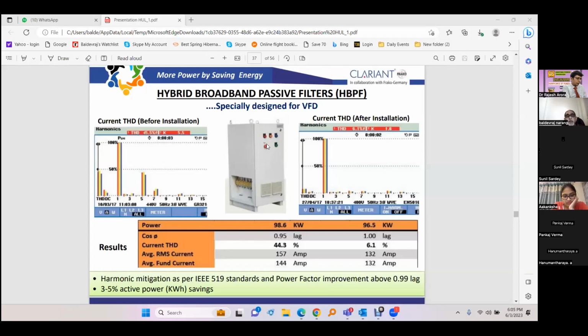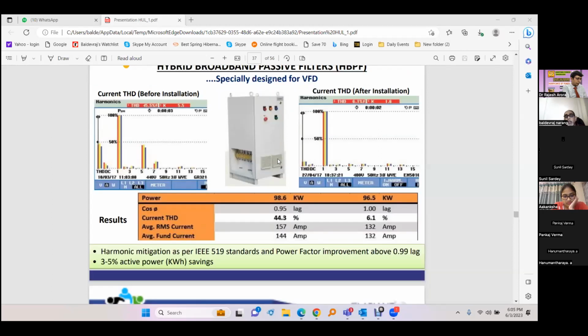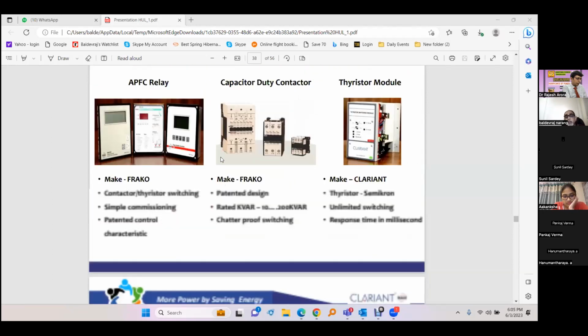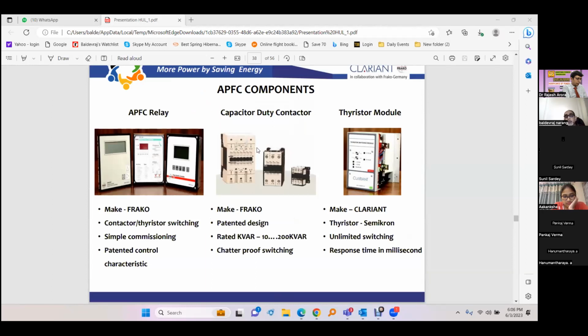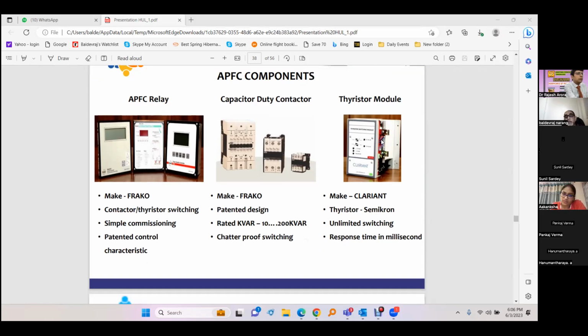Then these are APFC components. We have contactors, controllers and all. Now we use thyristors instead of contactors, and thyristors are zero crossover. They don't have any inrush current, so the capacitor life is improved, and the number of operations could be any amount. Contactors have a slow operation and will take around 1 minute to respond, but this can respond within 2 to 3 cycles. So we can give real-time correction with that.